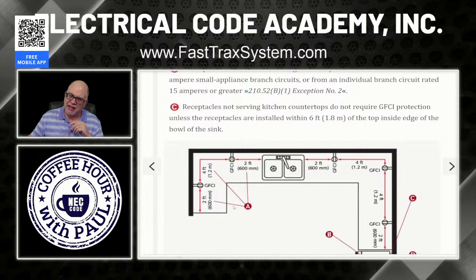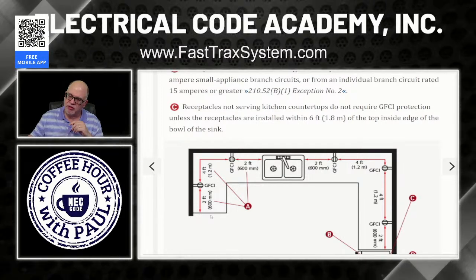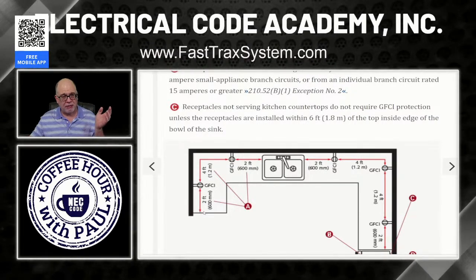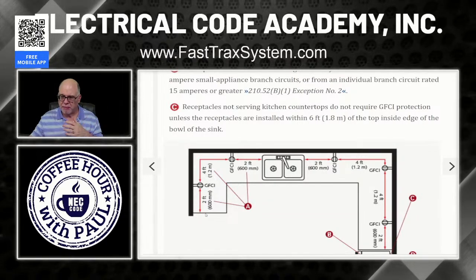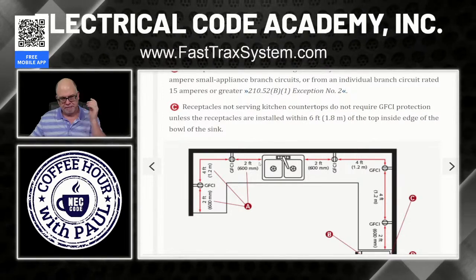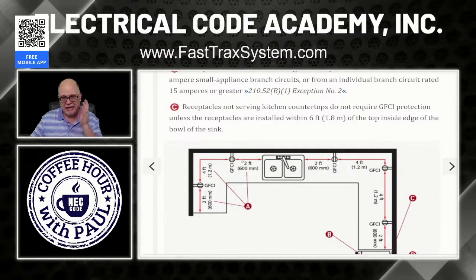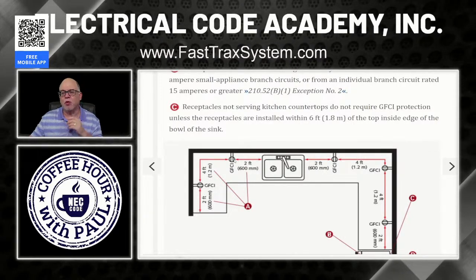Now here's the edge. Down here at the bottom, here's the edge of the counter. I have to have one within 2 feet of the edge. Kind of like a break in the wall line when we did the 6 foot, 12 foot. Same here. This is the edge of the counter. I have to have one within 2 feet. So I come in 2 feet, put one, then I can go 4 feet, put one. And if that one's also within 2 feet of the actual sink, then I'm okay. Can it be within 1 foot of the sink? Yep. Can it be 18 inches from the sink? Yep, that's fine. It just can't be more than 2 feet.